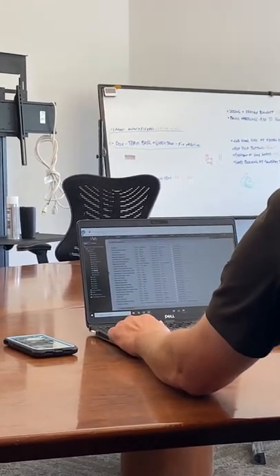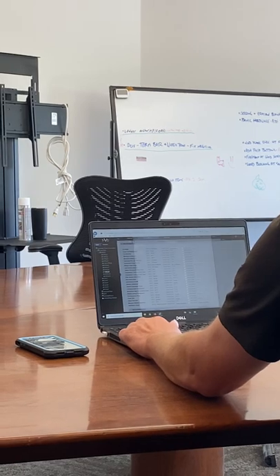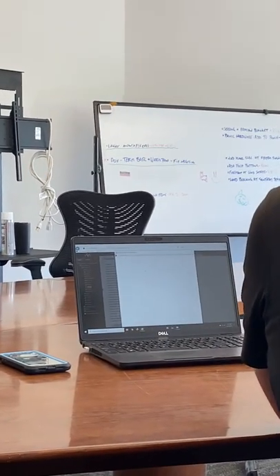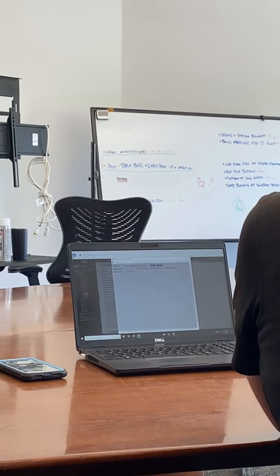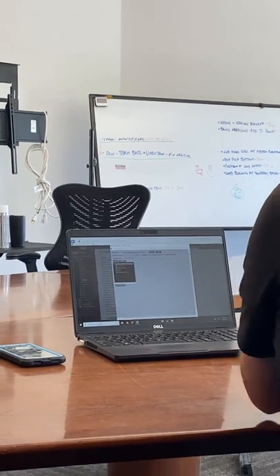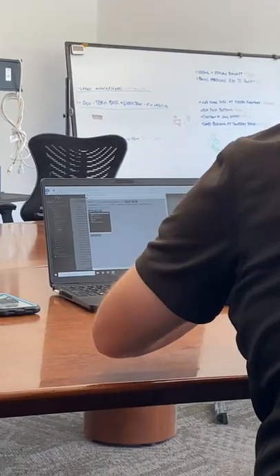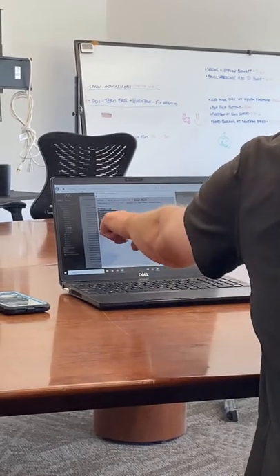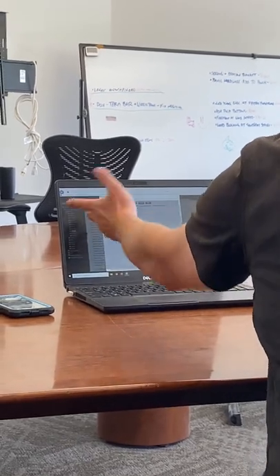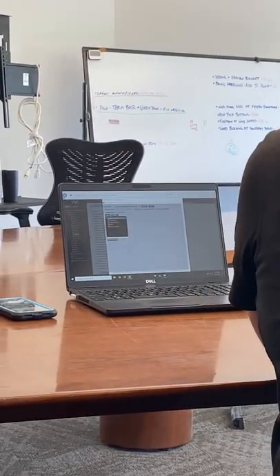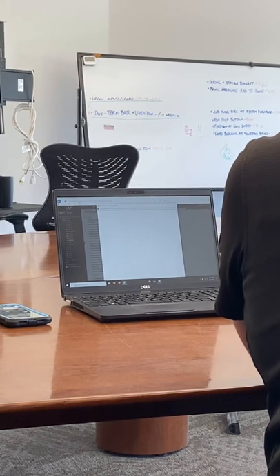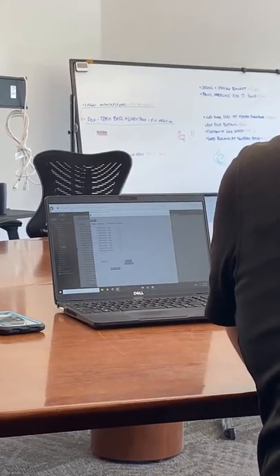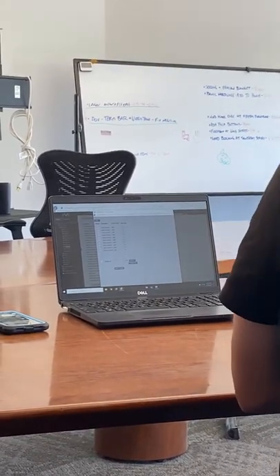So set point adjustment range — for any point that has a box like this and you want to global modify it, you just hold Alt and click on the box. It'll bring up this screen. It's asking where do you want us to look for things we can global modify, and you just always want to do the whole site — the whole building. So we hit Find All.